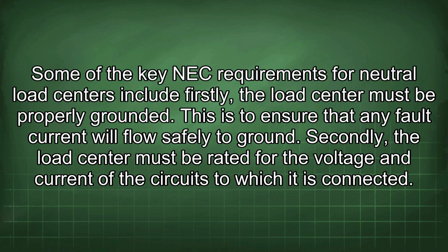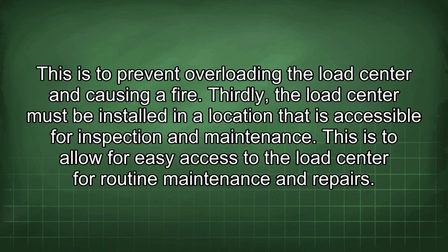Some of the key NEC requirements for neutral load centers include: firstly, the load center must be properly grounded. This is to ensure that any fault current will flow safely to ground. Secondly, the load center must be rated for the voltage and current of the circuits to which it is connected. This is to prevent overloading the load center and causing a fire. Thirdly, the load center must be installed in a location that is accessible for inspection and maintenance. This is to allow for easy access to the load center for routine maintenance and repairs.